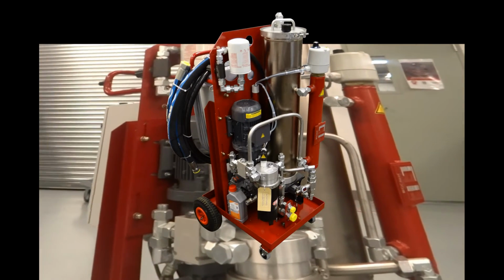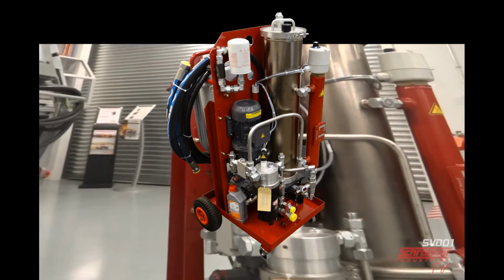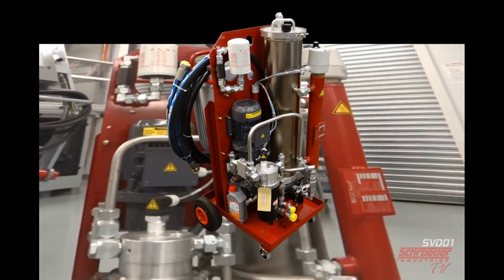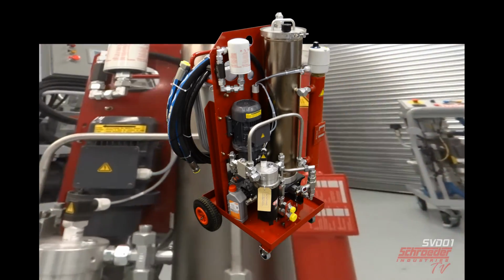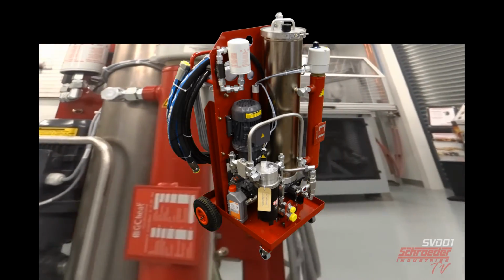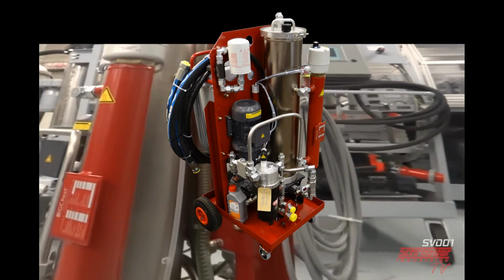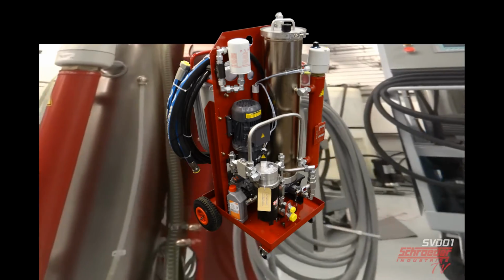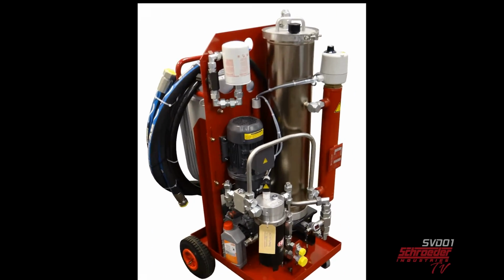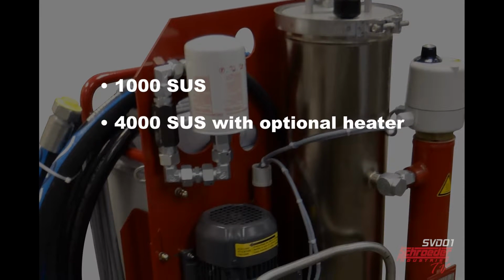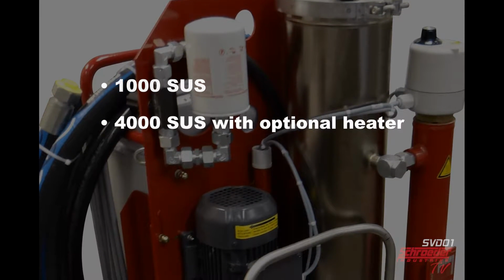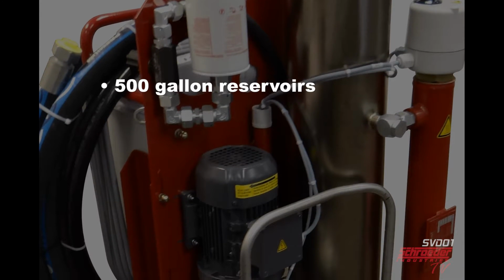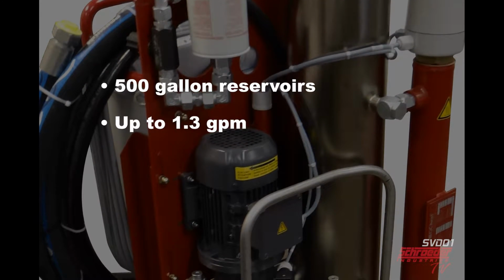The vacuum dehydrator, SVD01, serves to dewater, degas, and filter hydraulic and lubricating fluids. It works on the principle of vacuum dewatering to extract free and dissolved water, as well as free and dissolved gases. The viscosity rating of the SVD01 is 1000 SUS, or 4000 SUS with the optional heater. The SVD01 is recommended for up to 500-gallon reservoirs with a flow rate up to 1.3 GPM under normal water ingression rates.